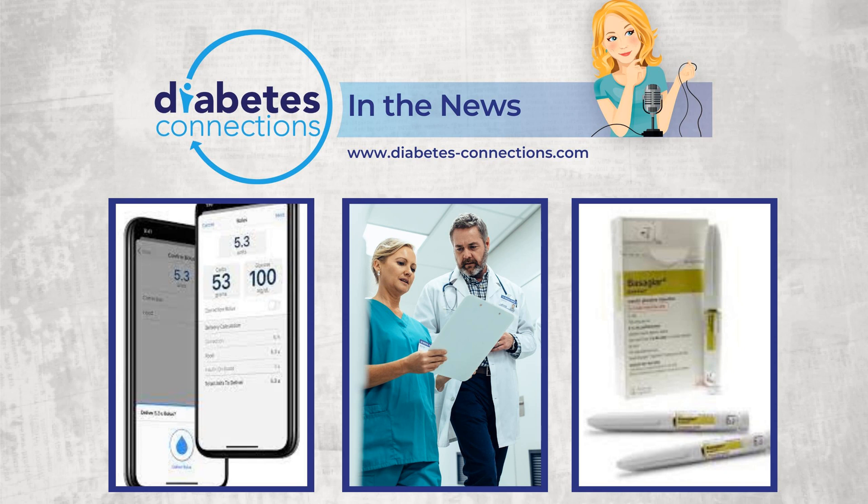Over in Europe, the Eversense E3 gets its CE mark — European approval. This is a partnership between Ascensia Diabetes Care and Senseonics. The E3 is the six-month version of the implantable CGM system. It's also approved for insulin treatment decisions, which is a switch from the XL version already available in Europe. The E3 was approved in the U.S. earlier this year. It should be distributed in Europe in the fall.